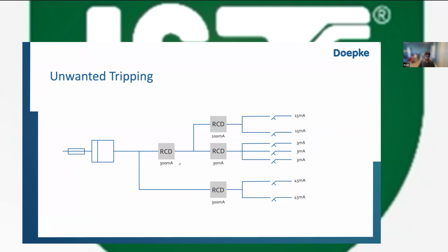So the first thing is you have to select the device correctly so that the frequency bands are taken care of, like we explained. And then you need to sectionalize. If you have a 100 milliampere RCD, 100 times 0.3 is 30 milliampere. So the sum of leakage current of all connected equipment downstream should not exceed 30 milliampere. 15 plus 15 is 30, this is fine. This is a 30 milliampere RCD. 30 times 0.3 is 9 milliampere. So 3, 3, 3, here it is 9. This is 300 milliampere. 300 milliampere times 0.3 is 90 milliampere. So 45, 45, 90. Now, importantly, this is also 300 milliampere. So 300 times 0.3 is 90. But the sum of this is actually 30 plus 9. So again, less than 90 milliampere.